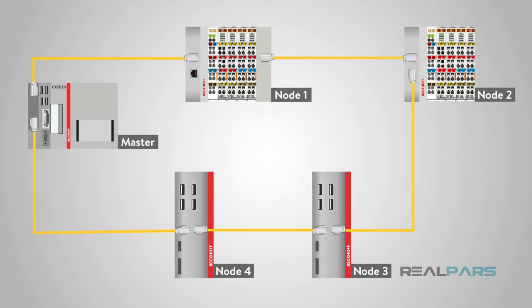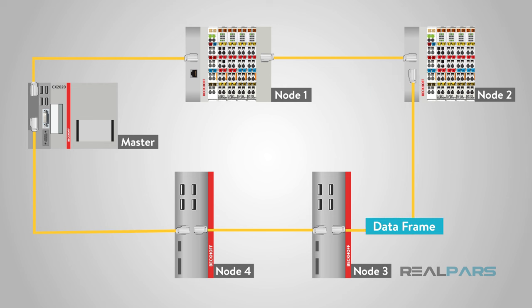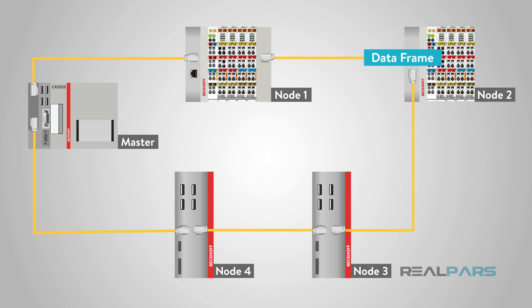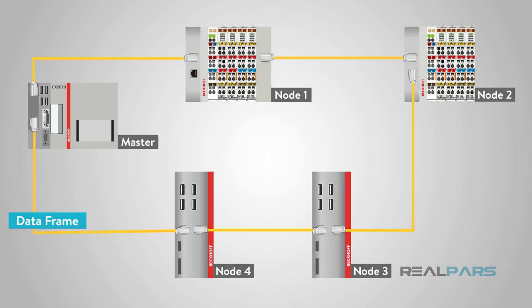With EtherCAT, the master sends data — possibly only a single frame for the entire node network — that will pass through each node. The master is the boss and is the only node allowed to send a frame. The frame is then forwarded downstream by each node in the network. This approach helps to assure real-time operation and avoids delays.